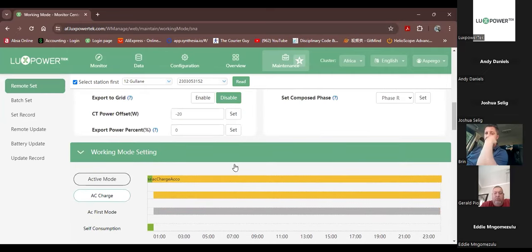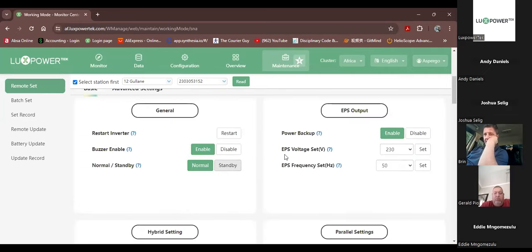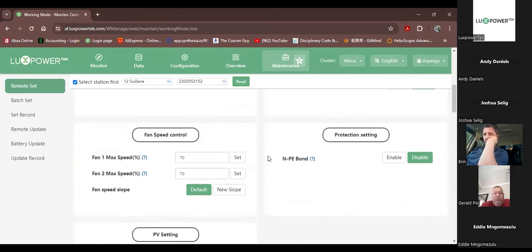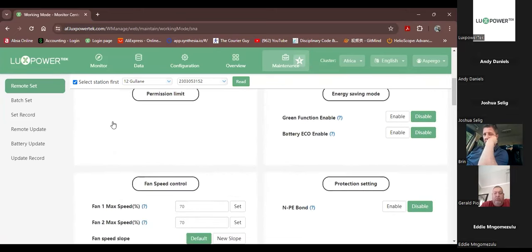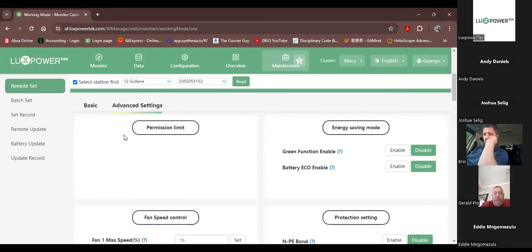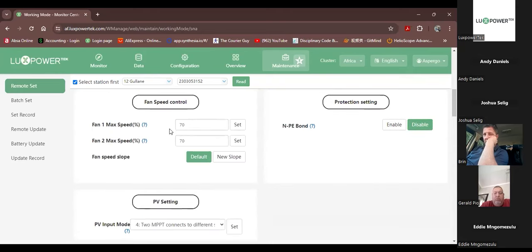Let's see what is in that quadrant in the advanced setting. Okay, so here in these two quadrants, they change. Remember that you've got two tabs here. So now these quadrants have changed. Here, the default setting for the fans is 70% for each one. And you can change the fan speed, but I don't recommend that you go any lower than 55% for either one of the settings, right? And then there's also a fan speed slope here. This one is currently set on the default, but you can obviously set a new slope.